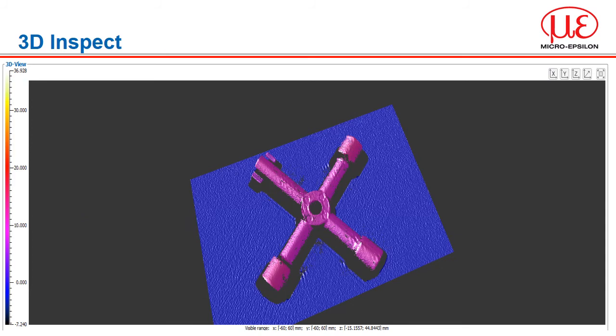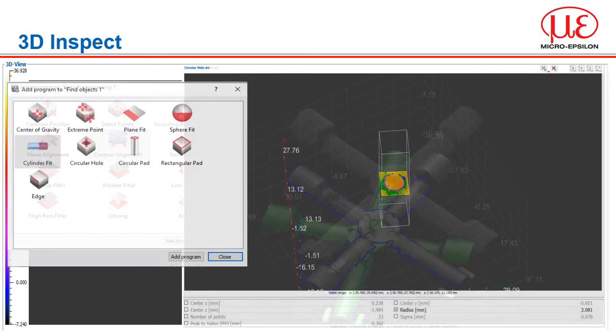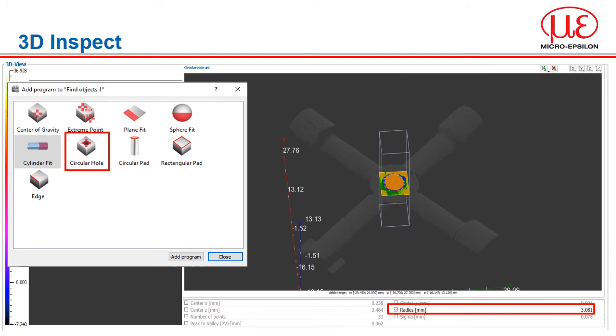So, if we take this object which is a utility tool, we are able to locate and orientate this part using the pre-processing functions. Which functions you use will depend on the target and application, but here I am using contour tracking to find and rotate the part to a position I can further inspect. Once we have the part in a location we want, we can then look to find features and take measurements — like, for example, measuring the centre hole. When an object is configured, a number of potential measurements are made available for you to select. In this example, radius is highlighted.